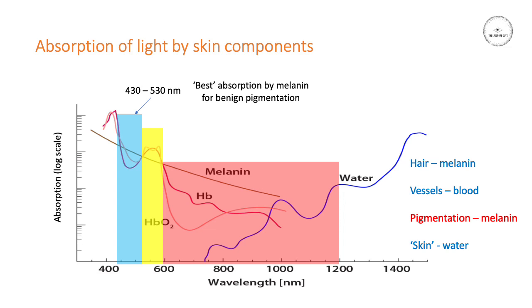And if you want to treat benign pigmentation and you're trying to target the melanin, then you could use a lower filter, somewhere between 430 and 530 nanometers. Down that end of the spectrum you'll get preferential absorption of melanin. It does conflict a little bit with blood, but you will get a fairly strong absorption. I should point out that the absorption scale on the y-axis is a logarithmic scale — so this is not linear, which makes a big, big difference.